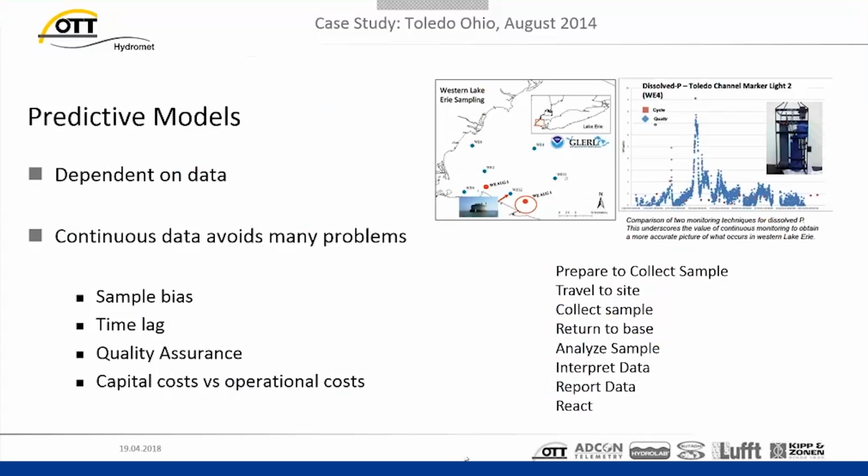And I just grabbed one of they make this point in this poster. Just the upper right-hand corner doesn't probably show you too well, but the cycle data sets, I think they actually have these backwards. The bluish diamonds is the cycle data every half hour, and then the grab samples are the ground truthing phosphate. If you look at the variance between them, you'll see that certainly in that middle part of the screen here, you've undersampled and you're not seeing quite a bit of the variance in the phosphate that you're getting if you look at it every half hour.